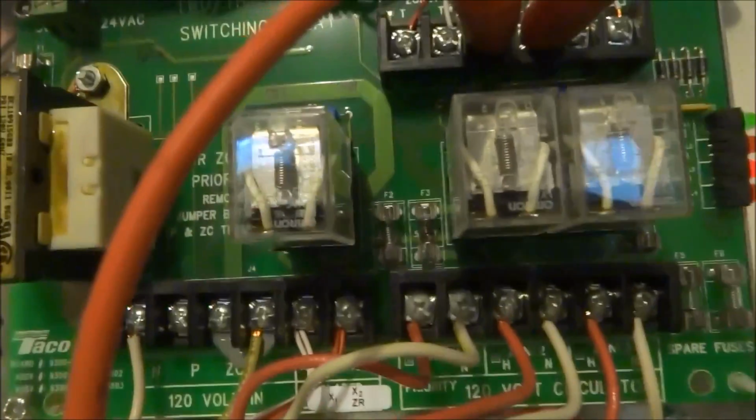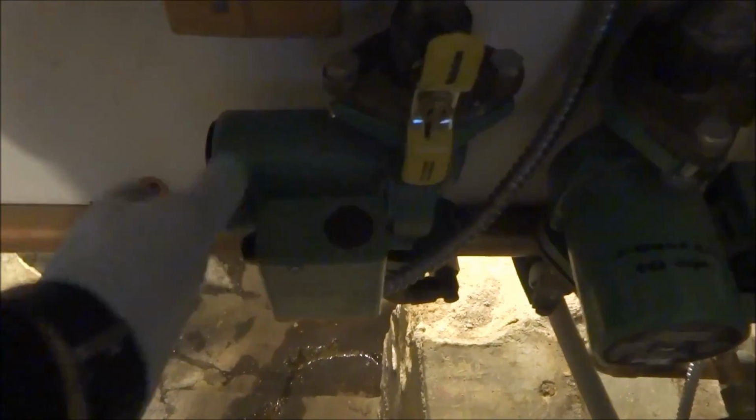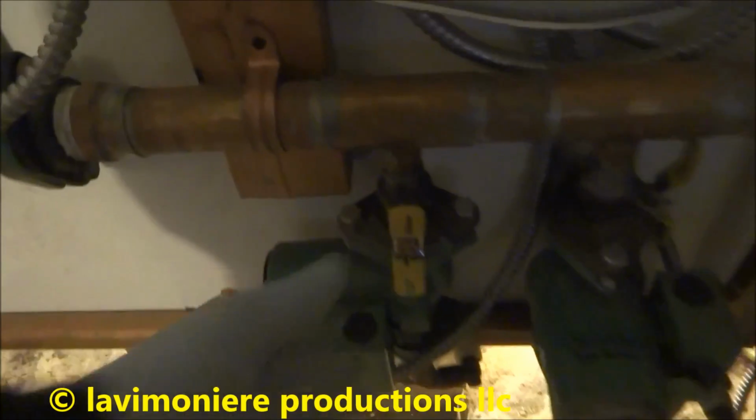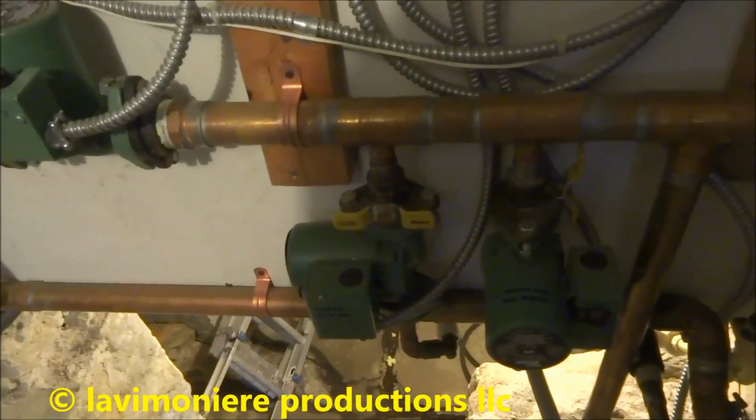Oh, it is. It blew the fuse. Must be a bad circulator, I was right. I seen the thing flash. It blew the fuse, so I gotta change it. I got one of them in the truck, 0015. This shouldn't be an issue.